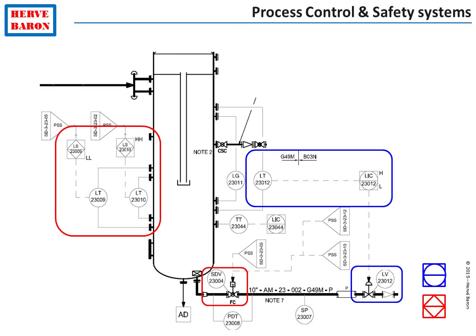The process control system and process safety system have completely different equipment — different sensors, controllers and final elements. For instance, the liquid level at the bottom of a column is controlled by a controller that is part of the process control system, shown with a circle, which acts on a level control valve to maintain a particular level. Should this controller or valve fail and the level fall too low, a separate level transmitter will pick it up and send a signal to the process shutdown system, which will close a shutdown valve to avoid gas blow-by to the downstream side.